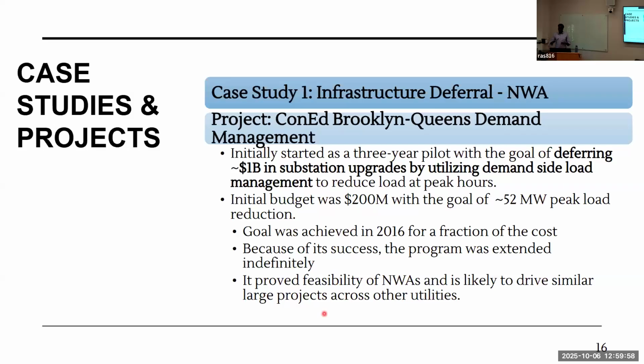During that time, your entire demand goes down. If you're doing that for multiple customers, and using other resources like EVs and batteries to discharge back to the grid locally - because these systems are constrained upstream of where you are as a customer - if you're reducing that local demand, it adds up to say 52 megawatts at that specific time, reducing the entire constraint on the grid. The peak times are normally just a few times a year, so they might call on you specifically 4 times a year, and in time they save a billion dollars of upgrades or defer it for a few years.